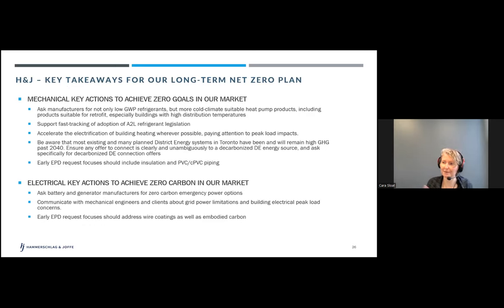Mechanically, we know that we have to ask manufacturers not only for low GWP refrigerants and EPDs, but we need more cold climate suitable heat pump products. We need products suitable for retrofit, especially for buildings with higher distribution temperatures in their hydronics. We need to support fast tracking of that A2L refrigerant legislation.